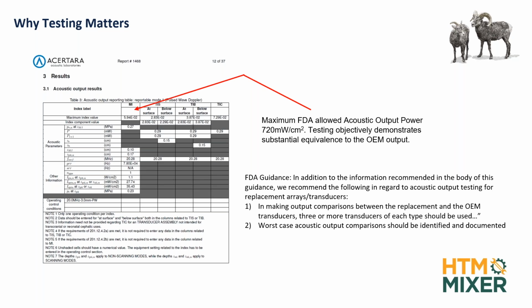ultrasound beam. So the maximum the FDA allows for acoustic output power is 720 milliwatts per square centimeter, and you have to be substantially below that. Again, because there's statistics and you have variance, you don't want to be right at the limit. Get any variance, you're going to pop over the limit. So almost every OEM that I've ever worked with, 40 years ago, usually drops it down to 500 max, so that their production variance will be okay.